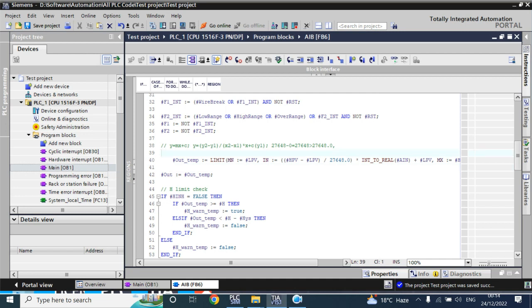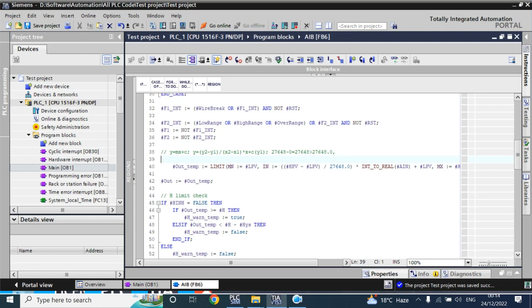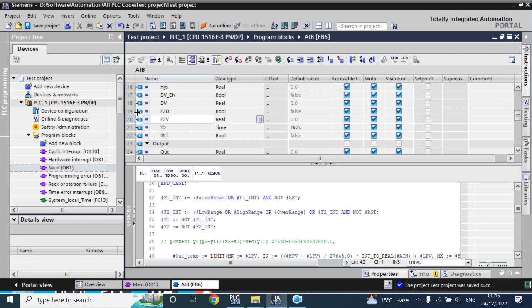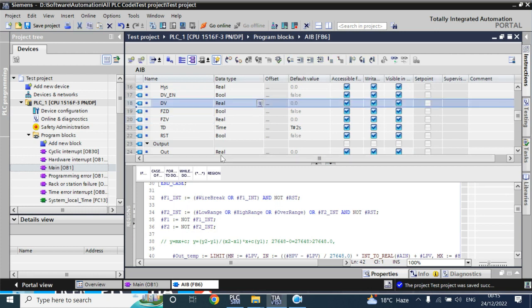We will write the code for this output value. We have three conditions. First condition: if a wire break or any overflow or underflow happens, the output value is copied from the default value. Second case: for maintenance purposes — if the DV enable has been chosen and a failure occurs, it will take the DV value.